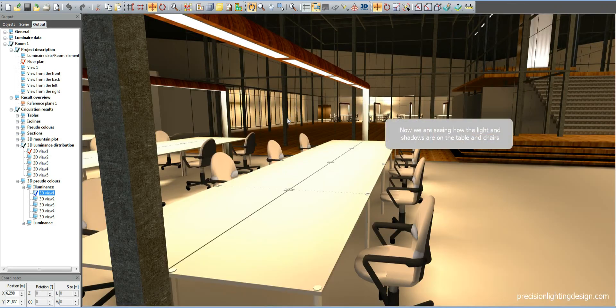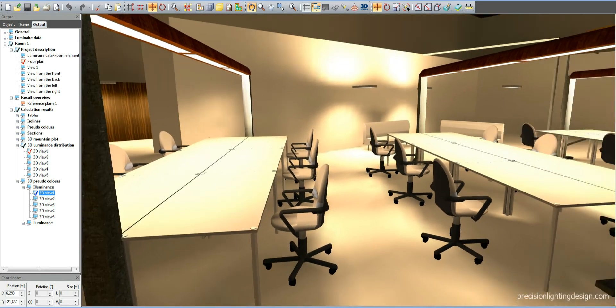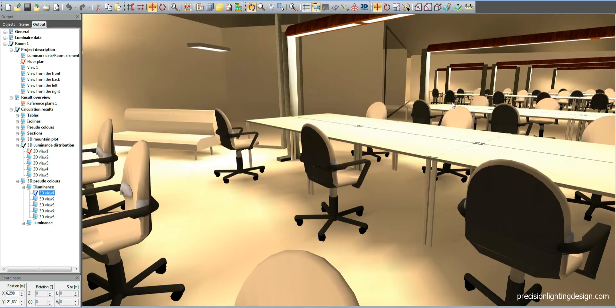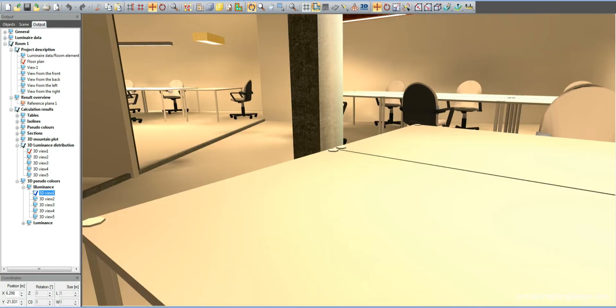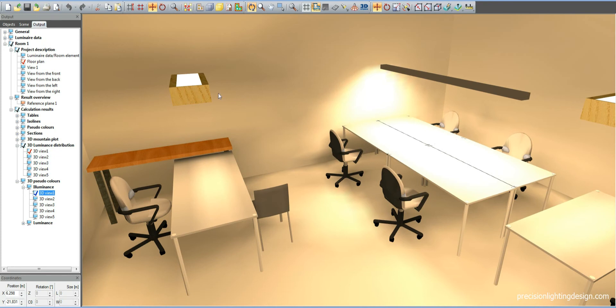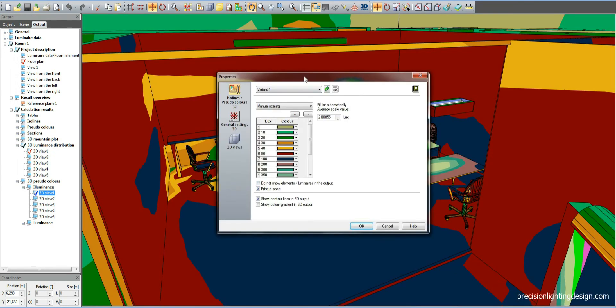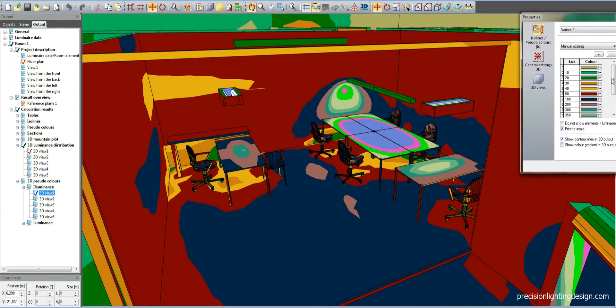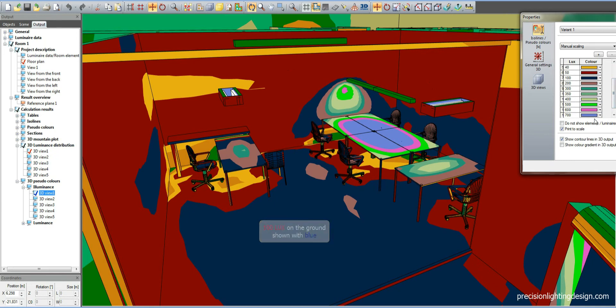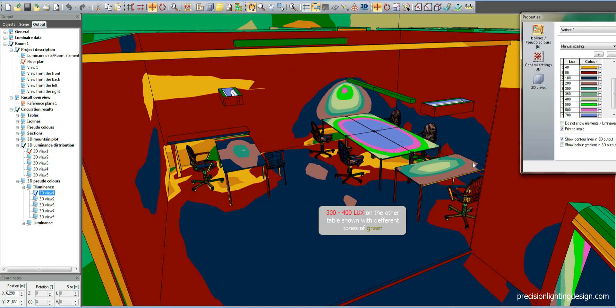Now we are seeing how the light and shadows look on the table and chairs. Let's proceed to the other areas. Now we are seeing how the room is lit. There is 100 lux on the floor, shown with blue. There is 700 lux on the table, shown with purple. There is 300 to 400 lux on the other table, shown with different tones of green.